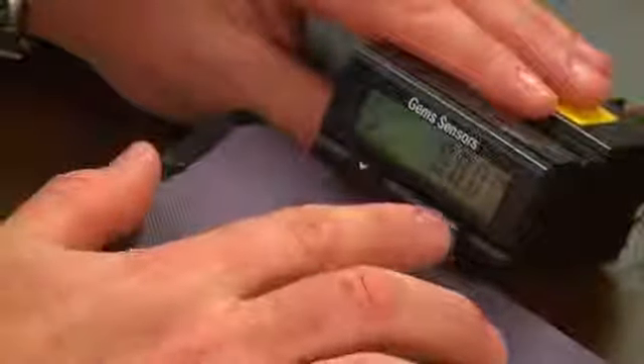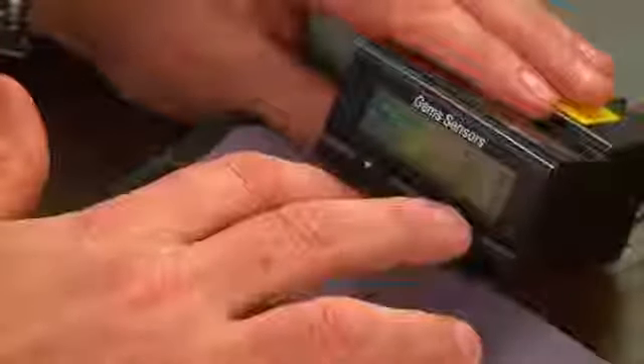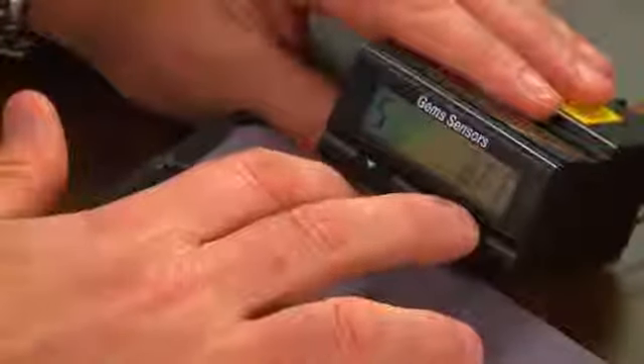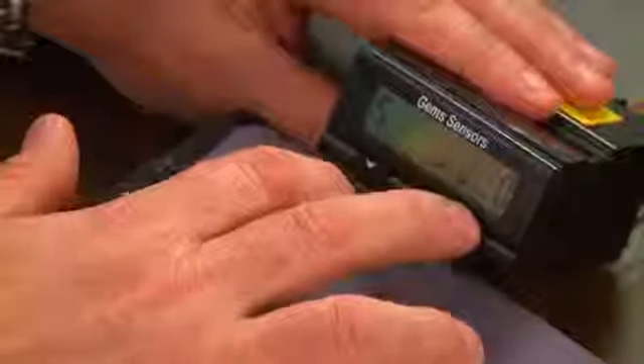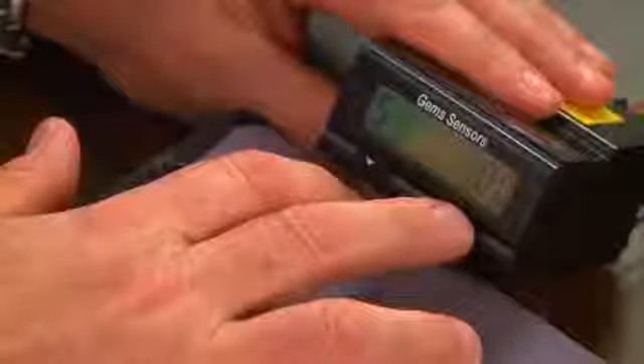Step 5 is the actual decimal point that you want the thing to read out when you're in rate. Such as right now, it's going to read 1.000 gallons per minute or 2.000 gallons per minute. Again, we can change that to nothing, off, 1 decimal place, 2 decimal places, 3 decimal places. The choice is yours, just toggling through that right-hand key. Let's leave it at 3 and move on to step 6.